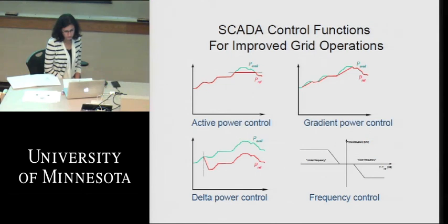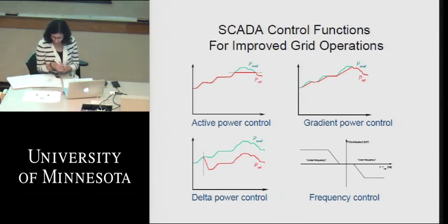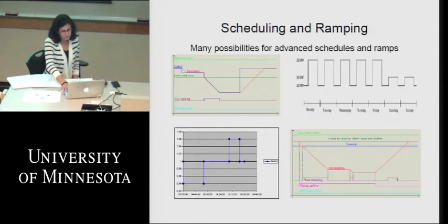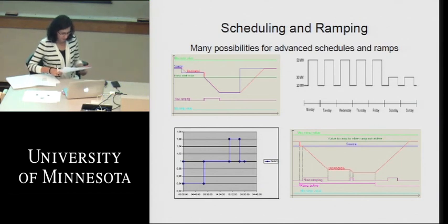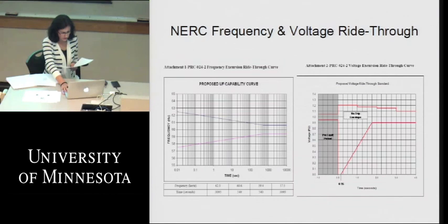If you look at that diagram after the presentation, you'll see the over and under frequency responses here. We can do different types of scheduling and ramping controls with these controllers. And we've got to meet the voltage and frequency criteria. They basically come from the North American Electric Reliability Council, who writes the standards for how the transmission operates. We've got to run in between those colored lines for frequency on the left and voltage on the right.